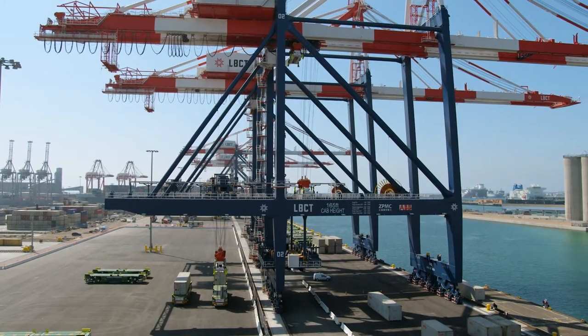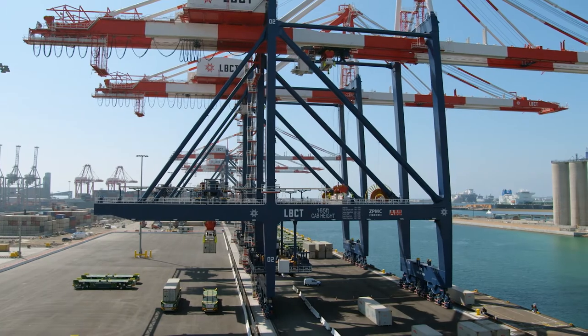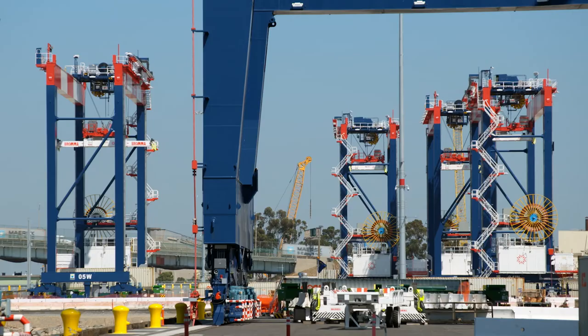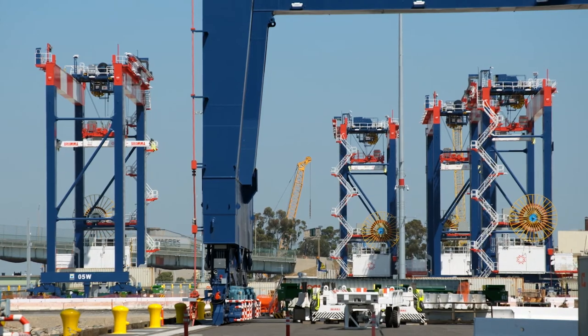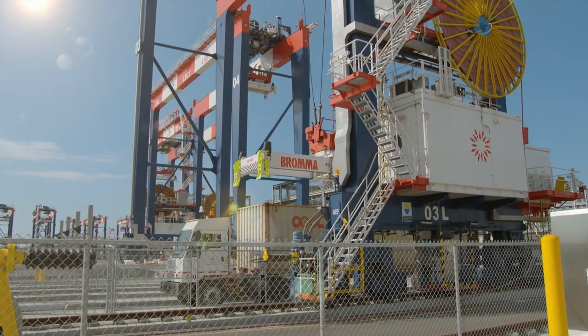We're using automated stacking cranes, semi-automated quay cranes, and automated guided vehicles throughout the entire facility. The cranes behind us — the ASCs — they have 20 milliseconds of delay. Anything over 20 milliseconds you start to get an alarm. At 100 milliseconds they shut down. You can't have downtime.